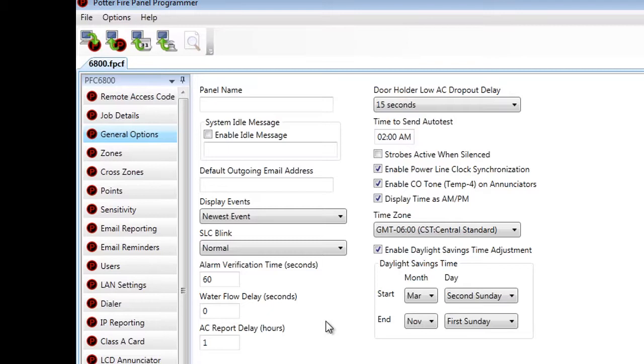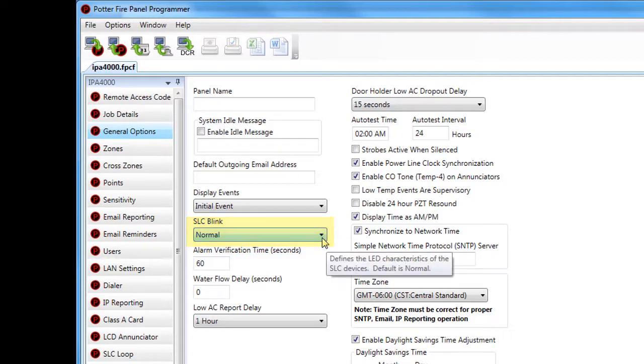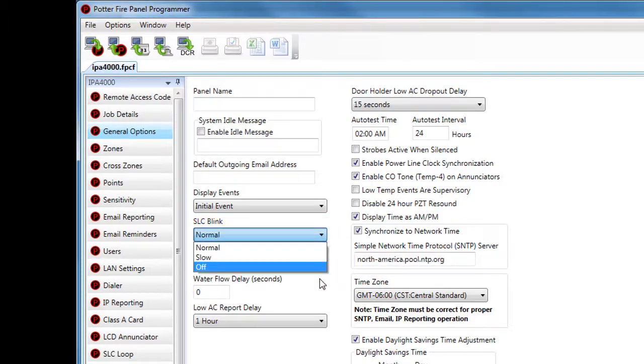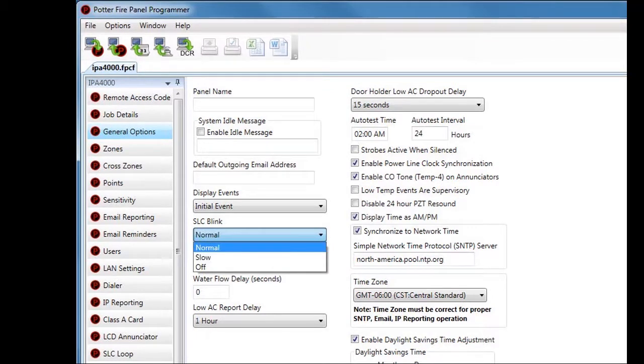The next option is SLC Blink. The default is Normal; other options from the dropdown are Slow and Off. SLC Blink refers to the blinking of the LED light on your SLC devices, sometimes called the heartbeat blink. Normal blink is about every four to five seconds when the fire alarm control panel polls the device. If you choose Slow, the LED will blink about every 30 seconds — the panel still polls the device every four to five seconds, but the LED only blinks every 30 seconds.